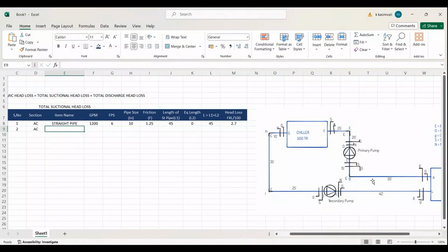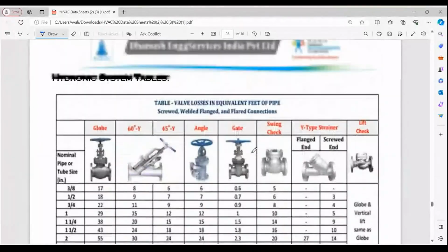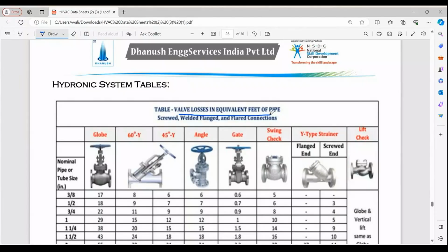Next we have the gate valve. So I'll go with the same values, 1200 GPM. The same flow will be there. FPS will be 6. Pipe size will be 10 and 1.25. The straight pipe length is 0. Here you will get the equivalent length. See here, valve losses in equivalent feet of the pipe. This is the gate valve.